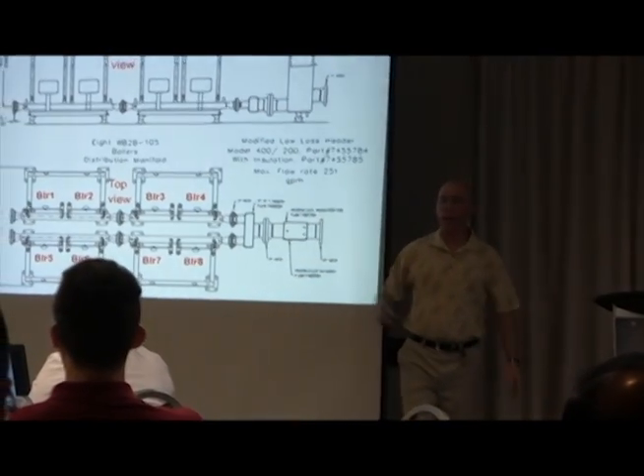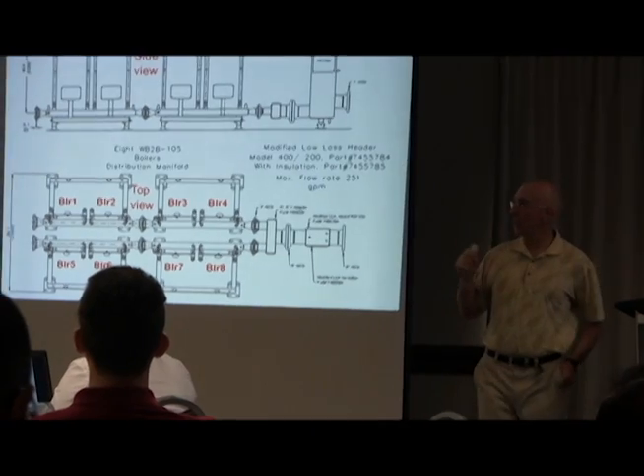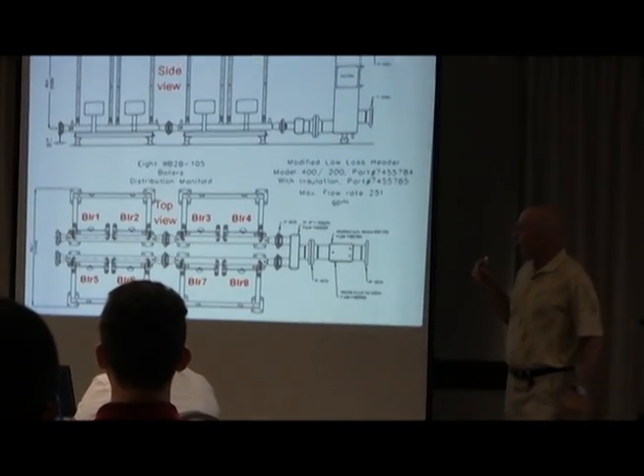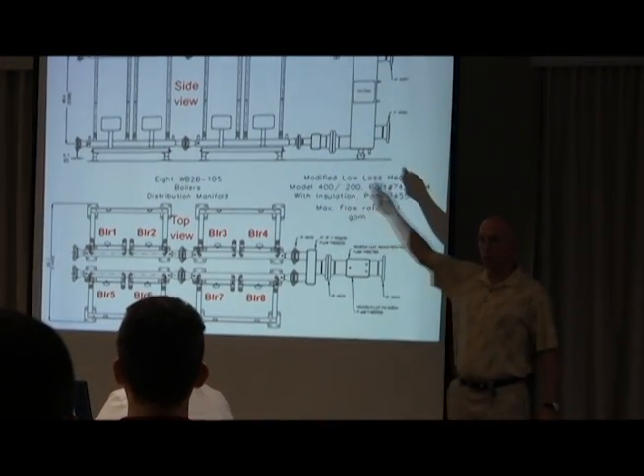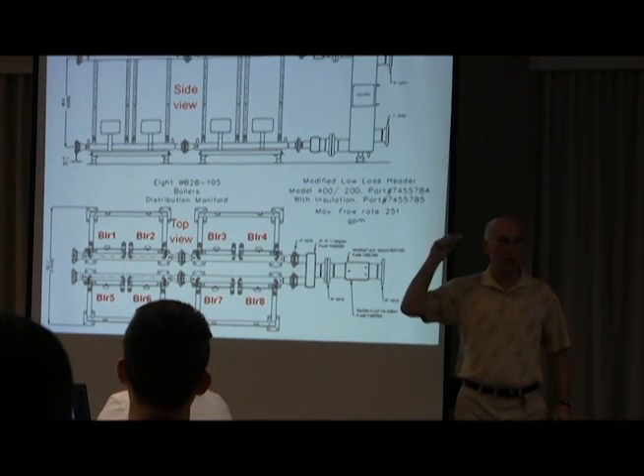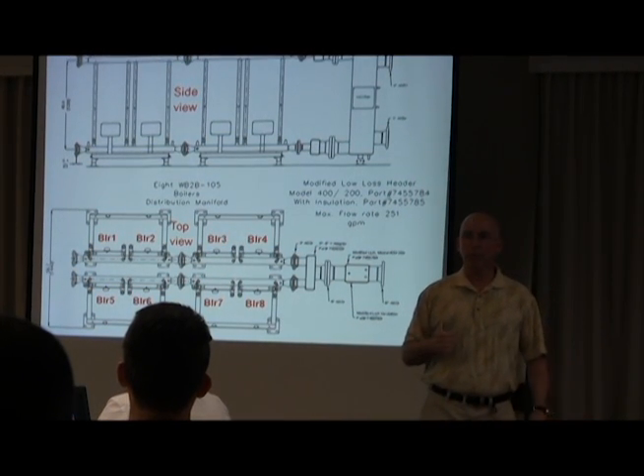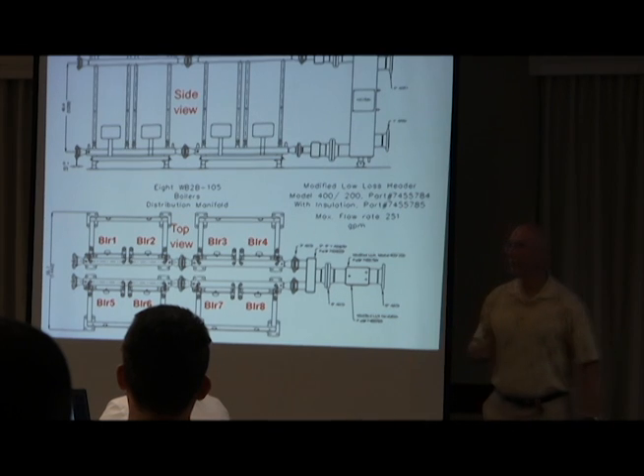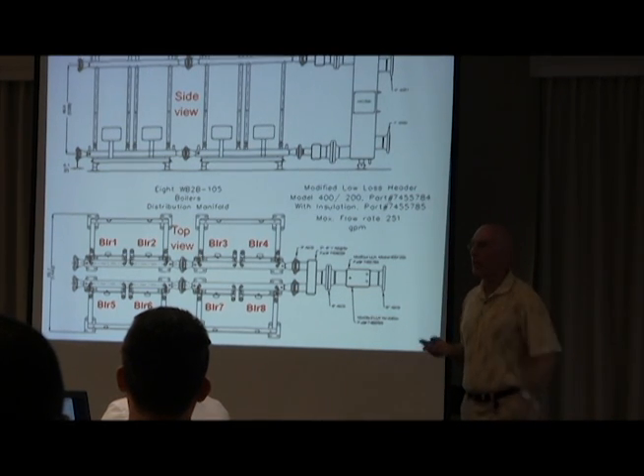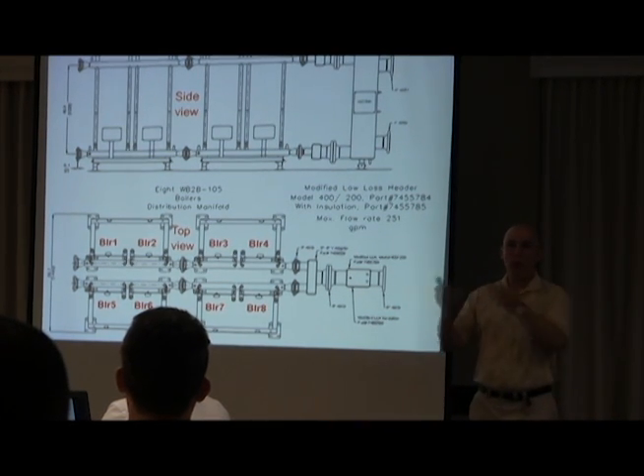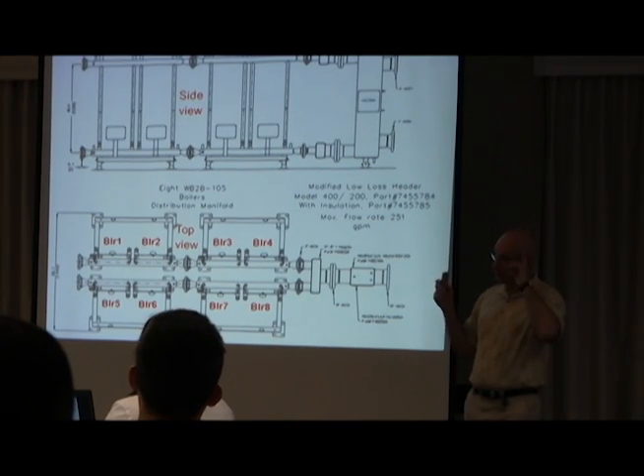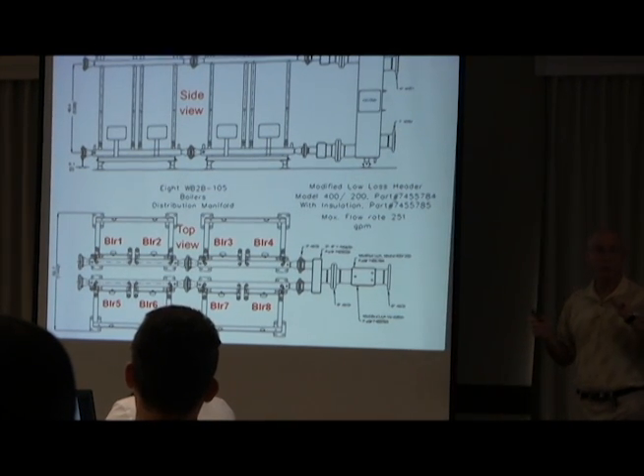Back to back, something I didn't mention but will now: if you do a cascade system like this, the boilers have to all be the same model. You can't put a 105 with a 45, or a 45 with a 60. You need 4 105s or 4 60s, all the same model number.